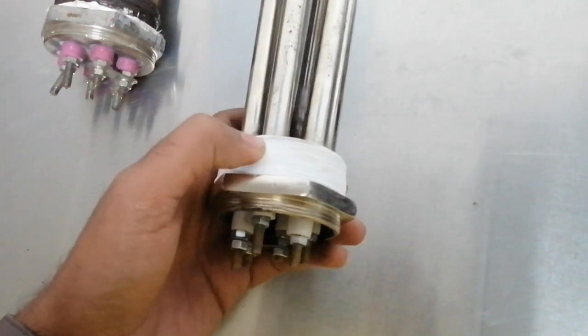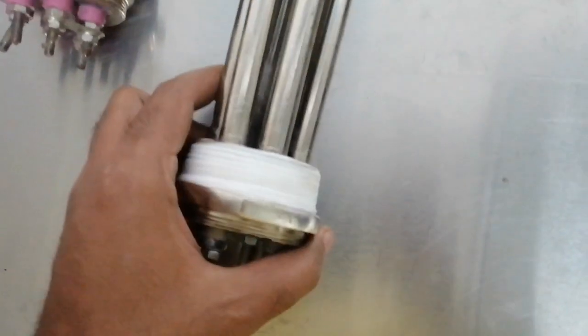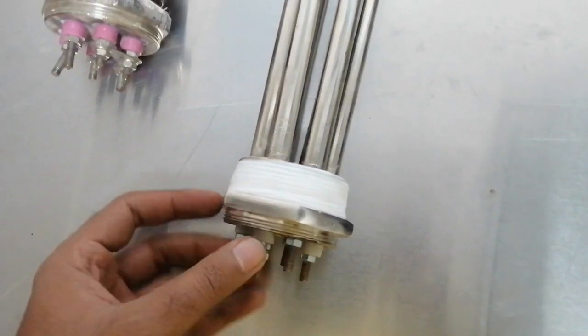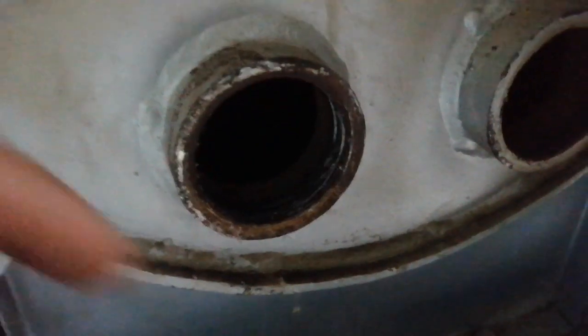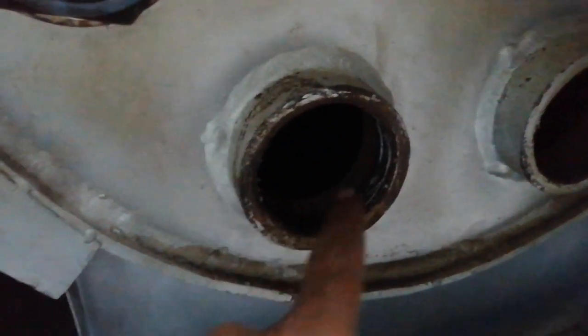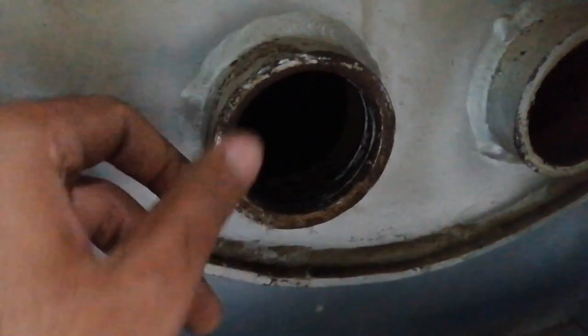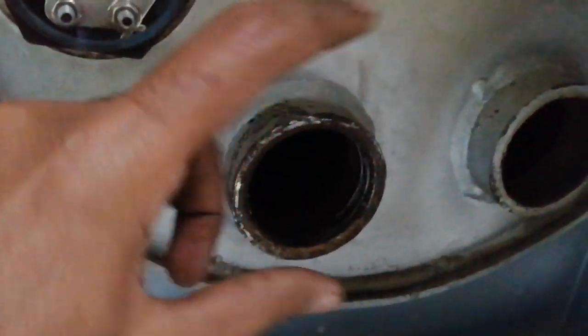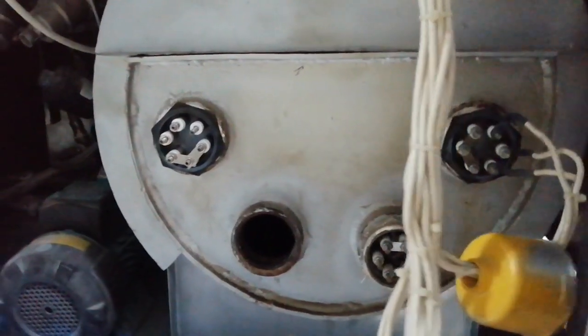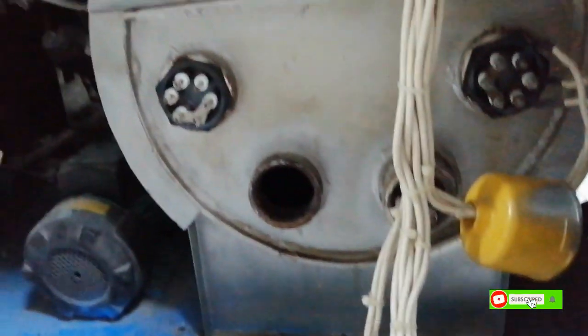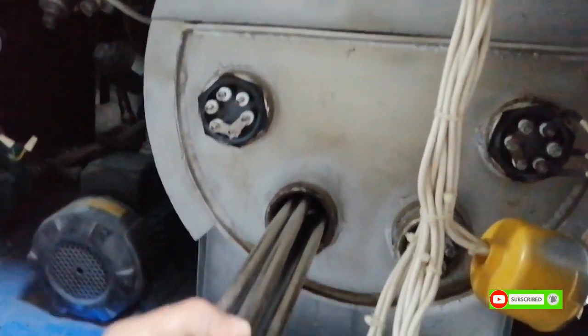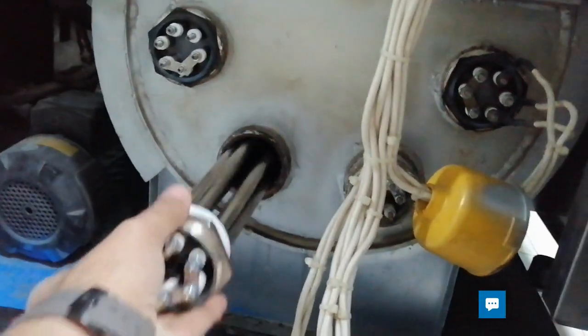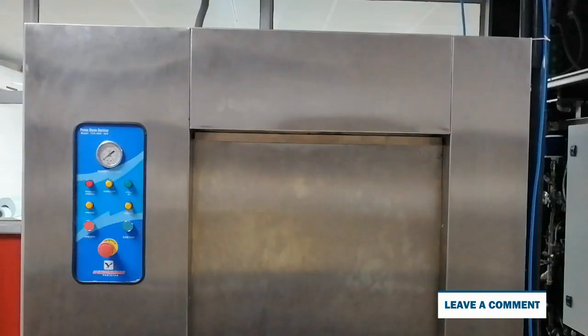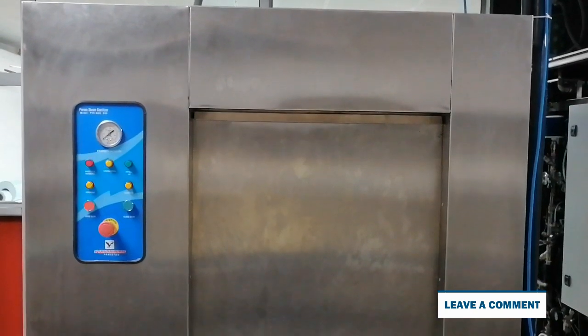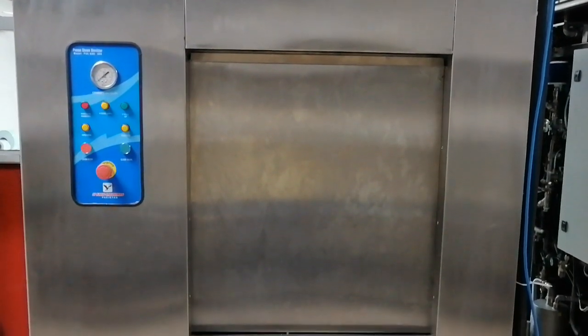The solid layer is inserted on the pipe, then we fit it on the main chamber. So here is the chamber. We just clean the chamber inside and fix the element as well. After inserting the element in the chamber, I fix the second element and then check the resistance. So here is the whole procedure to replace the element of the steam sterilizer.